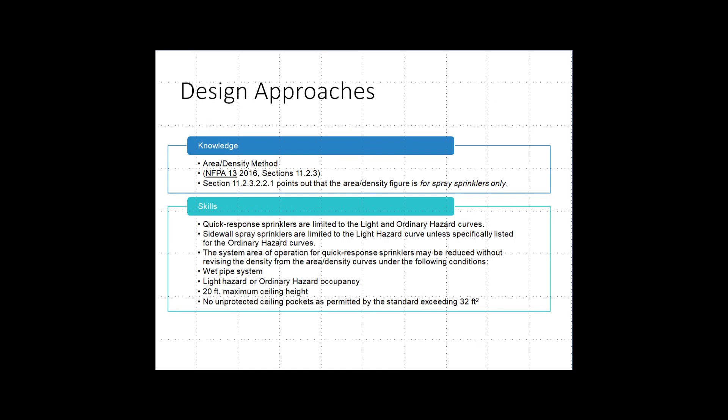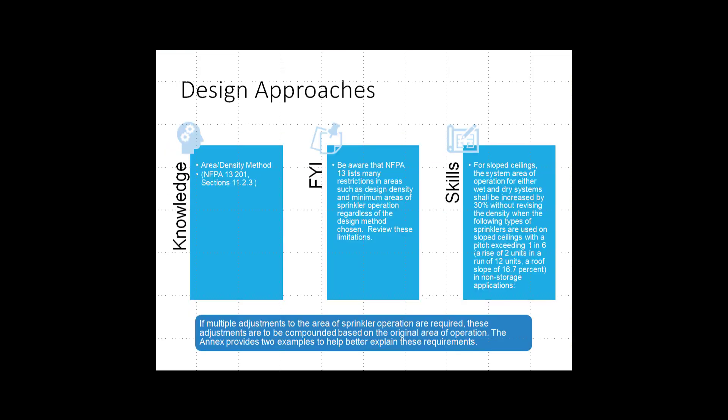Section 11.2.3.2.2.1 applies to spray sprinklers only. Remember to increase the area of operation 30% for dry systems and 30% for slopes exceeding 1 in 6 units, or 16.7% in non-storage applications.